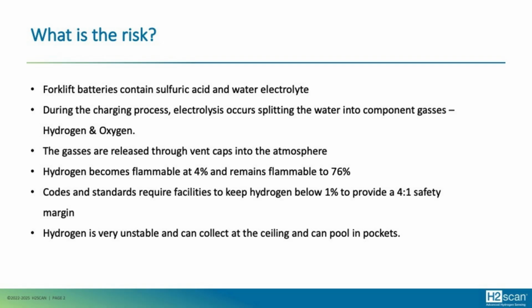Hydrogen is released through those vents and it can accumulate on the ceiling, since hydrogen is lighter than air. It could collect on top of a ceiling, or in pockets, or in raised parts of the ceiling, and can create hazards. Hydrogen becomes flammable at 4% and remains flammable all the way up to about 76%. This is why we have a lot of codes and standards that require facilities to keep hydrogen at a reasonable level. All of the codes and standards in the US say that we need to keep hydrogen below 1%. So this provides a 4-to-1 safety margin.